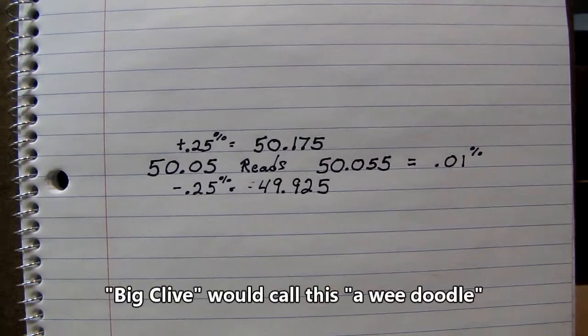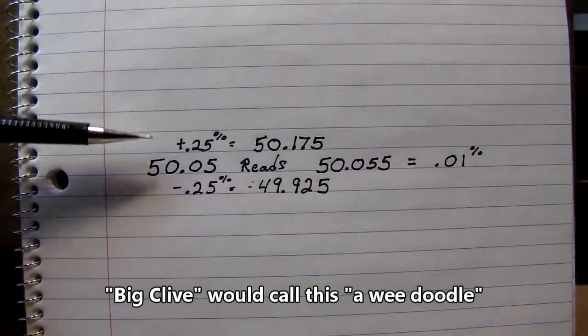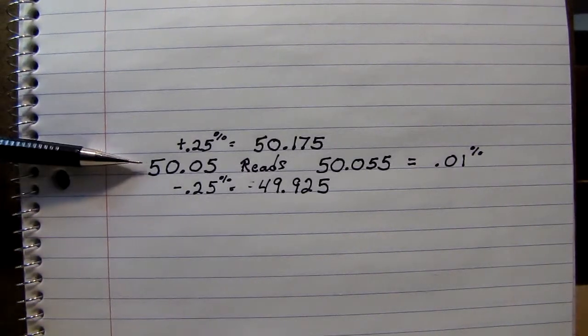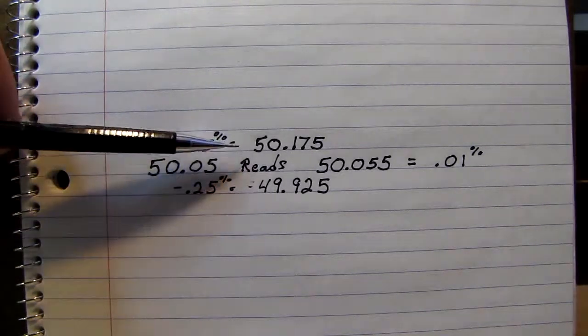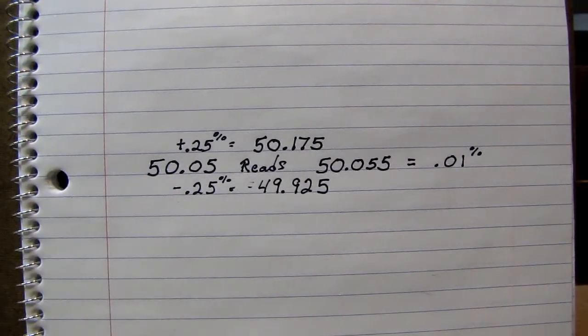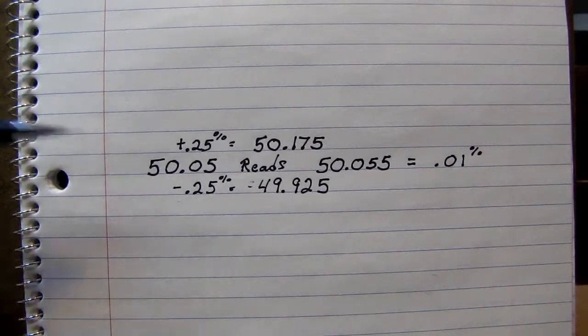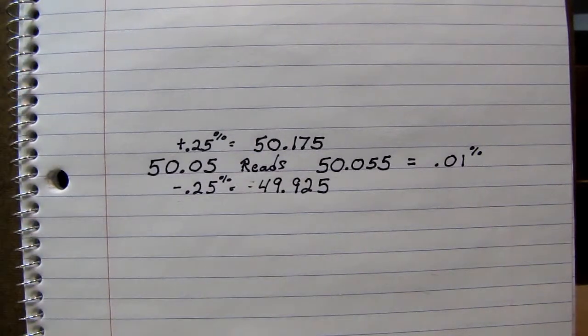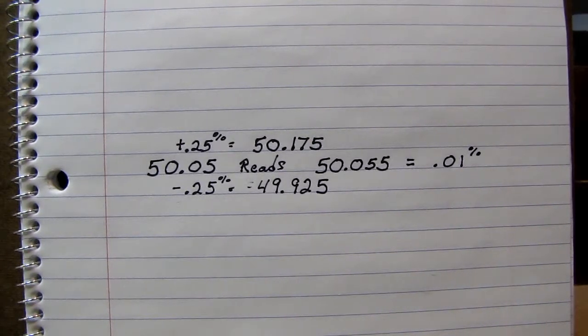Let's do the maths. If we consider the meter itself could be off as much as 0.25%, that means our 50.05 picofarad standard could read anywhere from 50.175 picofarads on the high side to 49.925 picofarads on the low side. However, our 50.05 picofarad standard is reading 50.055 picofarads, which is a mere 0.01% error. That leads me to believe this bridge is operating superbly, and I can trust it as a transfer reference to my other equipment.